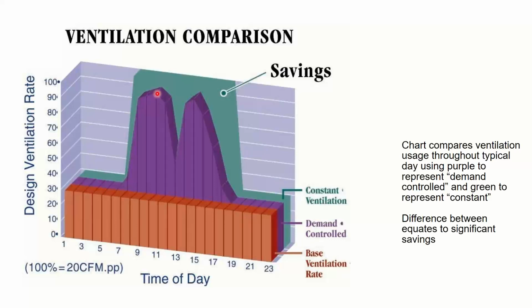But everything between purple, actual CO2 data, and green, code required ventilation, is my savings. The code allows me to go below the code required outdoor ventilation rates that I showed you early on if I put a CO2 sensor in and do it dynamically on the fly. So as people leave, throttle it back to save energy. As people come back in, open it back up to get the maximum amount of ventilation that I need for all of those people. If the classroom has 5 people in it or 35 people in it, it's a different amount of fresh air that I'm going to need.